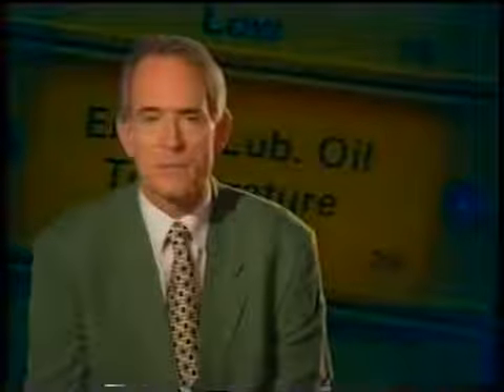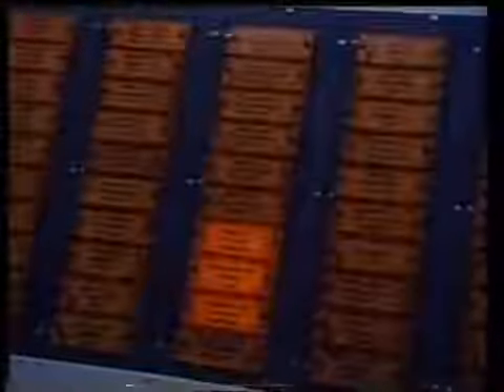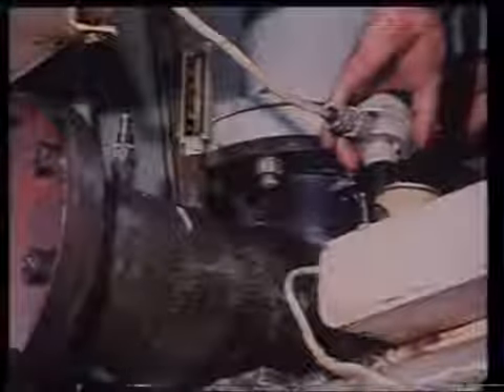Now we've come to UMS operation. UMS stands for Unattended Machinery Space. There are several alarm circuits associated with the main engine and the auxiliary machines, their lubrication and cooling systems. Their operation is dependent on a series of pressure switches, flow switches, level switches, or temperature switches, which must function correctly for the ship to remain in classification. These are usually set and tested at the periodic engine survey and should only be touched if malfunction occurs. Test the circuitry for open circuit or short circuit and replace any faulty sensor unit or switch.